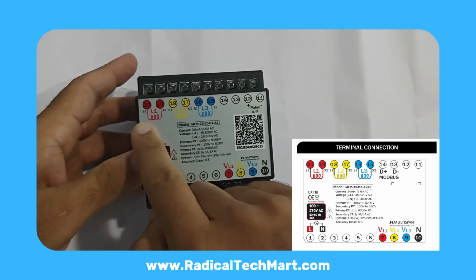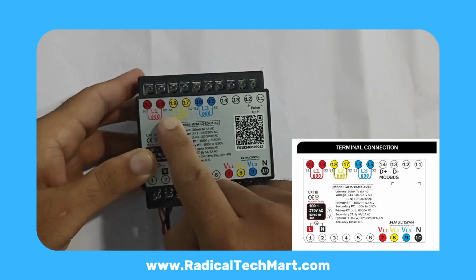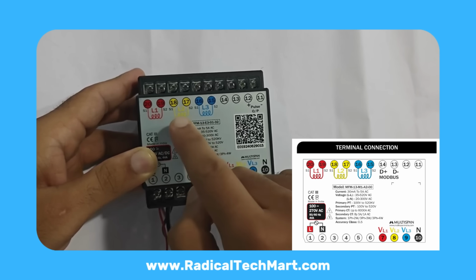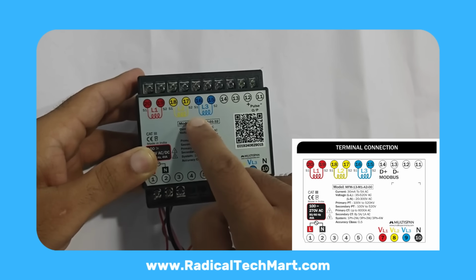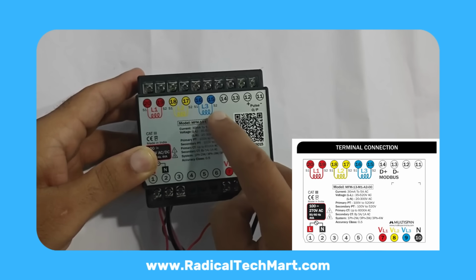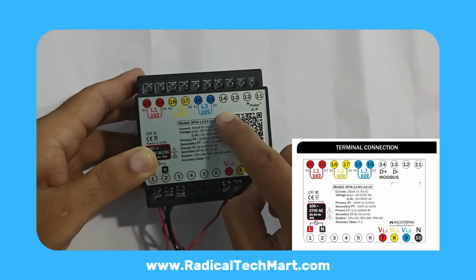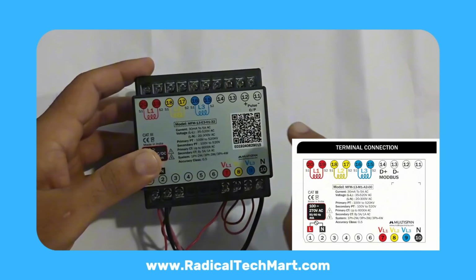On the top terminals, terminals 20 and 19 are CT secondary, S1, S2 for R phase. Terminals 18 and 17 are CT secondary for Y phase. Terminals 16 and 15 are CT secondary for B phase. So your 3 CT secondary wires will come here as S1, S2 pairs.